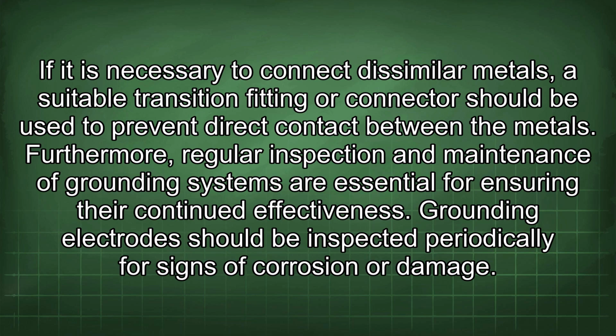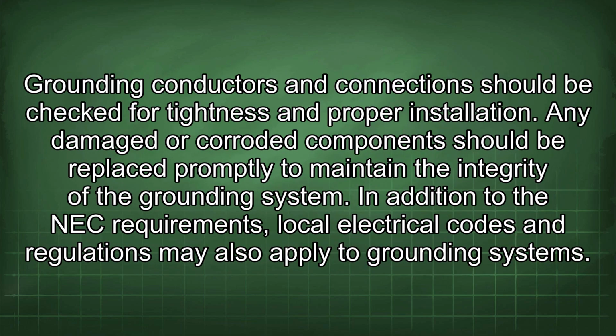Furthermore, regular inspection and maintenance of grounding systems are essential for ensuring their continued effectiveness. Grounding electrodes should be inspected periodically for signs of corrosion or damage. Grounding conductors and connections should be checked for tightness and proper installation. Any damaged or corroded components should be replaced promptly to maintain the integrity of the grounding system.